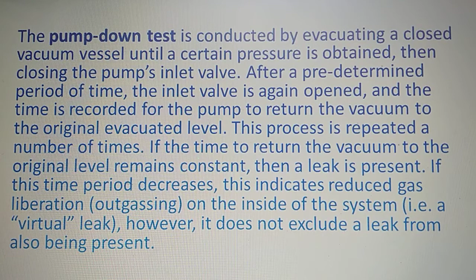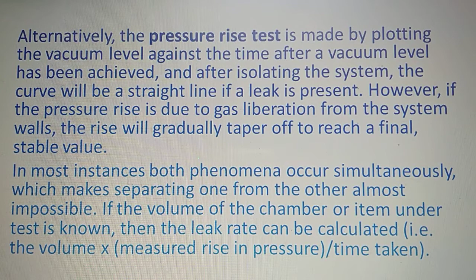Next is the pressure rise test. This test is made by plotting the vacuum level against time after a vacuum level has been achieved and the system has been isolated. The curve will be a straight line if a leak is present. However, if the pressure rise is due to gas liberation from the system walls, then the rise will gradually taper off to reach a stable value. In most cases, both phenomena occur simultaneously, which makes separating one from the other almost impossible. If the volume of the chamber or item under test is known, then the leak rate can be calculated. That is, volume times measured rise in pressure divided by time taken. This gives you the leak rate.